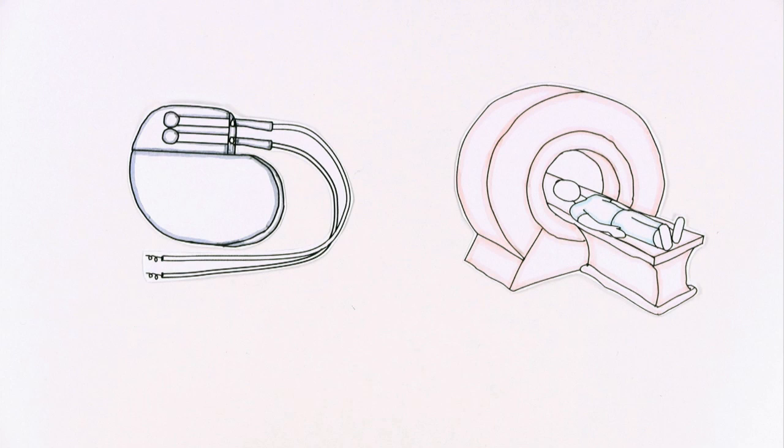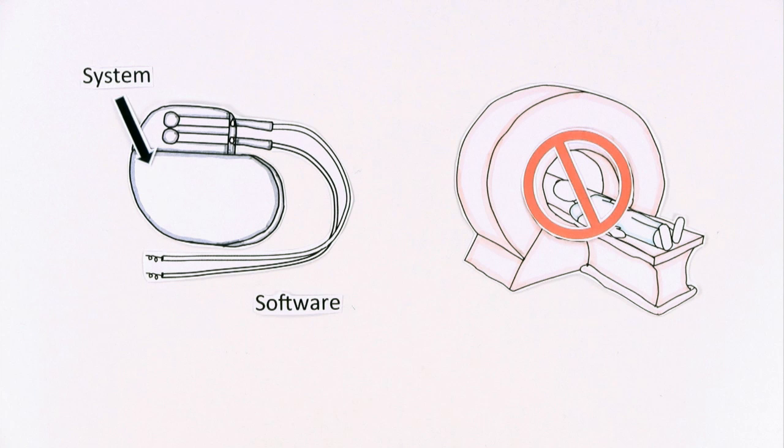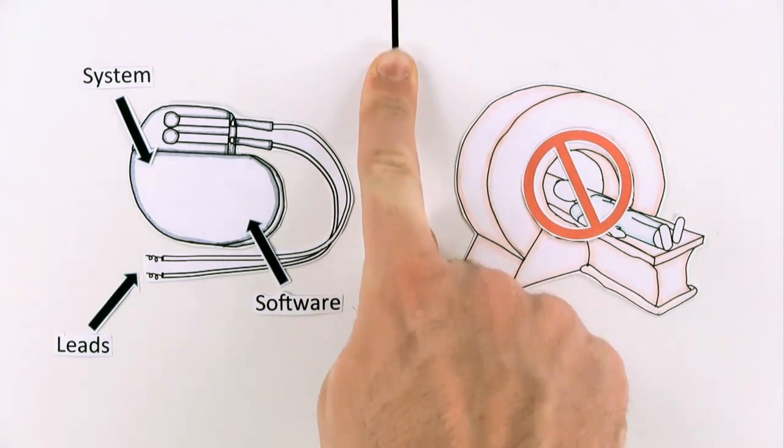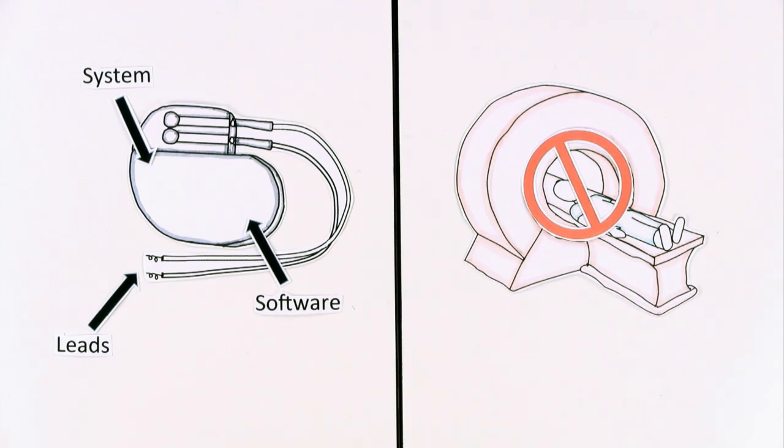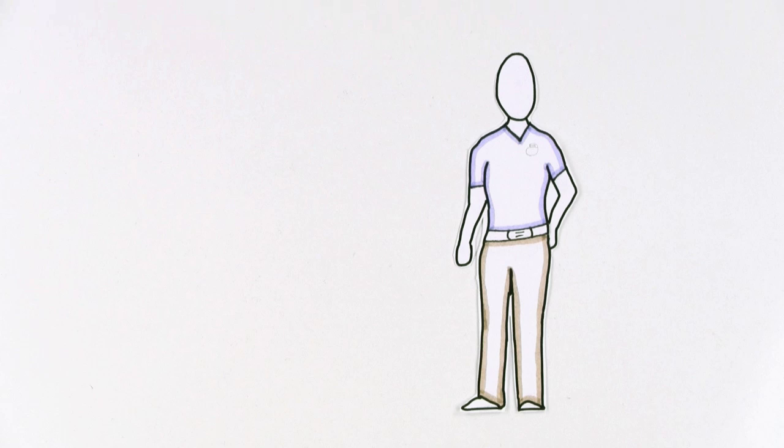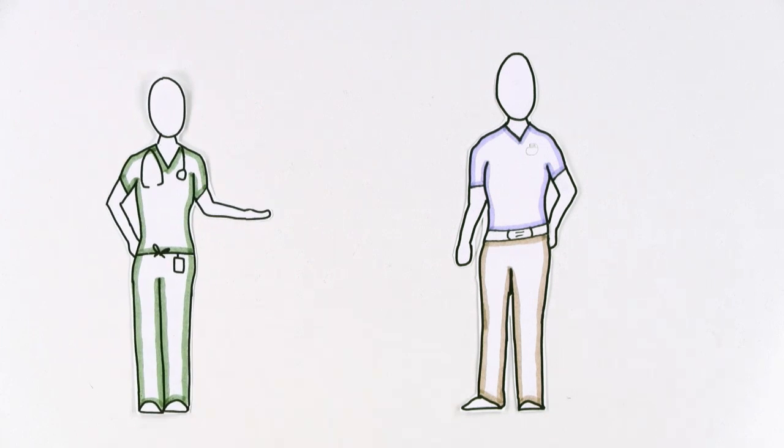Originally, pacemakers were not designed for MRI use. The system, software, and even leads all had the possibility to behave badly in an MRI, making MRI a problem for pacemaker patients. But her doctor had good news.